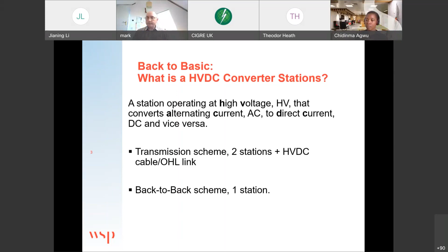So the technology that's usually used inside an HVDC converter station. You'd have heard the terms from my earlier presenters, my colleagues, saying LCC or VSC. At the very basis of this, you have your line commutated converter, which is based on thyristor-based technology. And on the other hand, you've got VSCs, which are your voltage source converters, which are based on IGBTs.